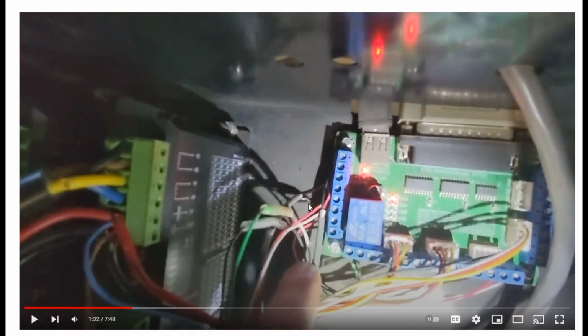I know he's got crimp connections over here. That should never be done. You never want to splice wires. I get that question a lot. Should I splice a spindle cable together? No. That's the simple answer. You would never, ever, ever splice a three-phase cable together. What you do is replace it with the correct length. Or you just measure correctly the first time. The first thing I tell my guys that are trying to measure for the correct length of a spindle cable is simulate the cable with string.